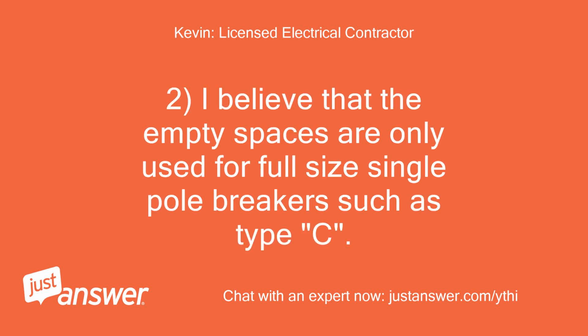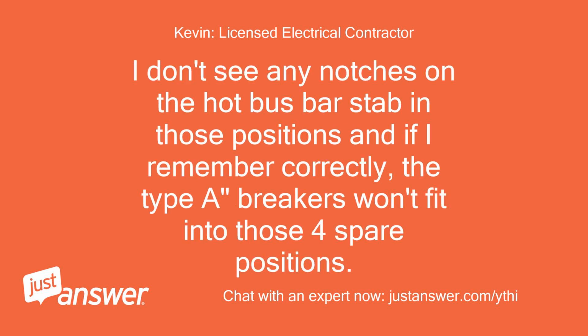2. I believe that the empty spaces are only used for full-size single-pole breakers such as Type C. I don't see any notches on the hot bus bar stab in those positions, and if I remember correctly, the Type A breakers won't fit into those 4 spare positions. I'm pretty sure they are reserved for full-size Type C only, but it's been many years since I've added circuits to a Challenger panel.